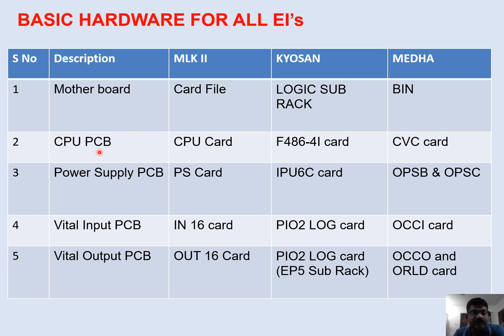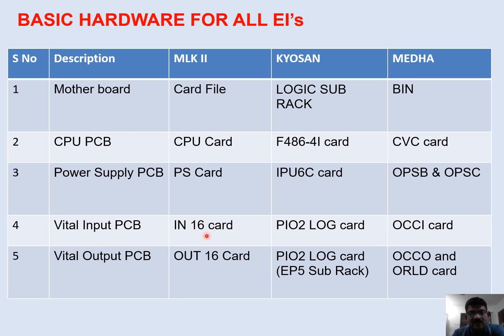The CPU PCB: in Microlog 2 it is called the CPU card, in Kyosan the same is called F486-4I, and in MEDHA it is called the CVC card. For the power supply PCB: in Microlog 2 it is called the PS card, in Kyosan it is IPU-6C card, and in MEDHA it is OPSB and OPSC. For vital input cards: in Microlog 2 it is the IN-16 card where 16 inputs can be given to each card, in Kyosan it is the PI-O2 log card, while in MEDHA it is called the OCCI card.